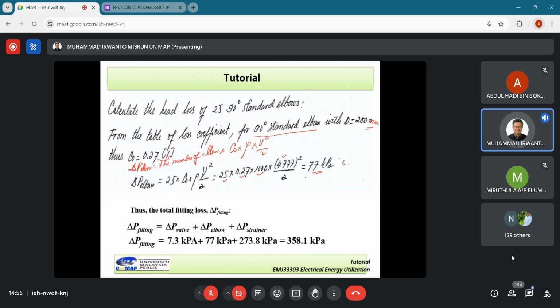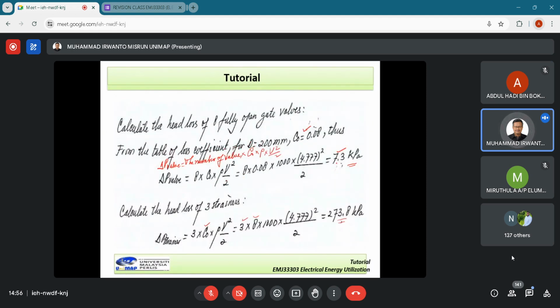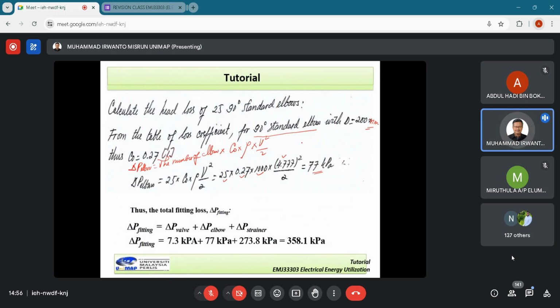Now we can find the total fitting loss. Delta P fitting is given by the fitting loss for the valve, for the elbow, and for the strainer: valve 7.3, strainer 273.8, and elbow 77.